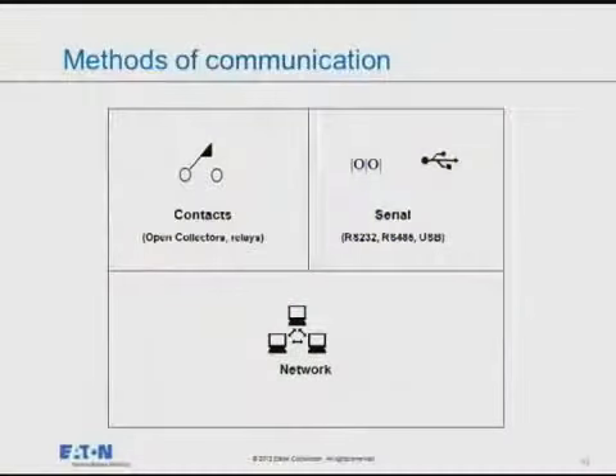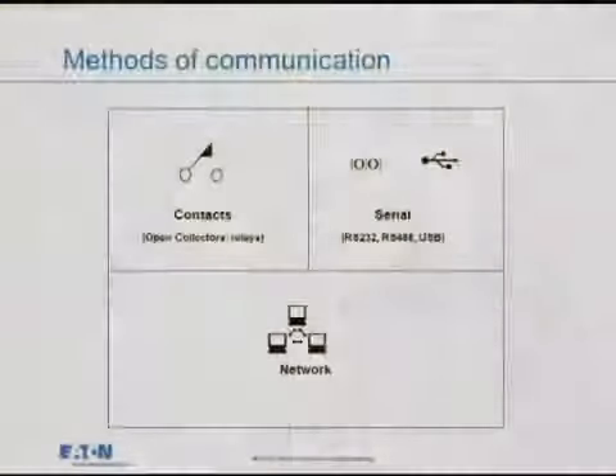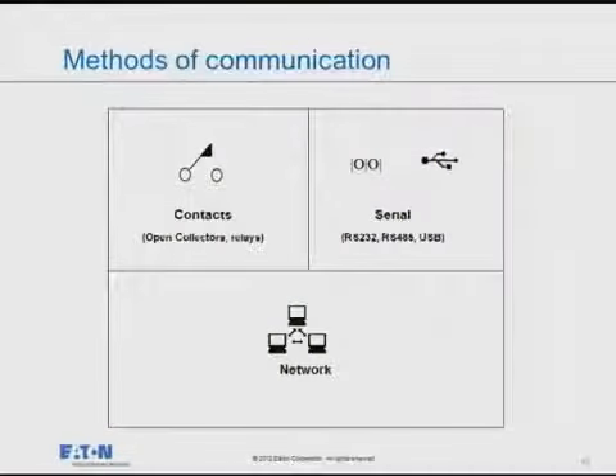So how do we communicate to UPSs out there? Really three fundamental means: contacts, also called summary alarms, open collectors from transistorized relays, form C, and industrial relays for 120 volt rated applications—numerous options for a yes, no, or relay indication. Second is serial: RS-232, RS-485, USB, point-to-point, peer-to-peer, collecting data from the UPS. Third is the network piece, which I'll break down in more detail.